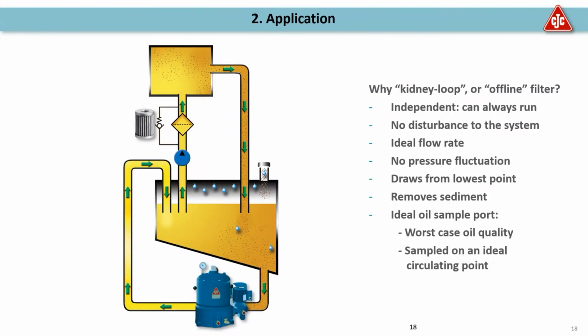It draws from the lowest point of the reservoir. It removes sediment, and it provides for an ideal oil sample port. What you're getting is the worst case oil quality, but sampled on an ideal circulating point.